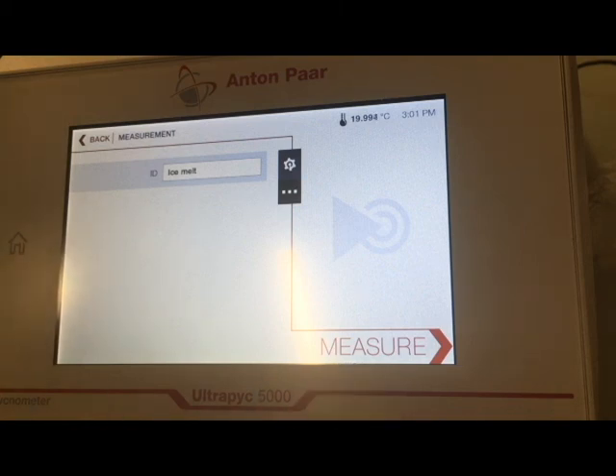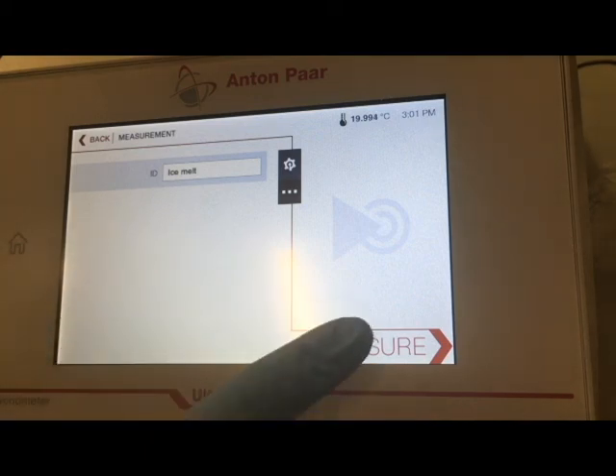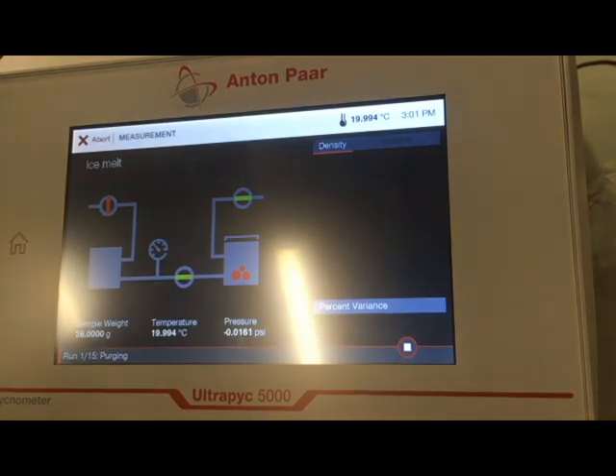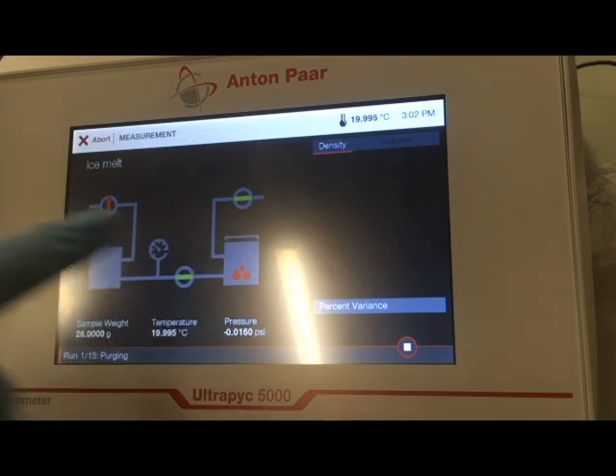If you are waiting for your temperature, I would recommend giving it a minimum of 20 minutes to make sure that it is nice and stable before moving forward with your measurement, to allow your measurement the highest chance to succeed. So we're going to click Measure, and it shows this little schematic of the device.